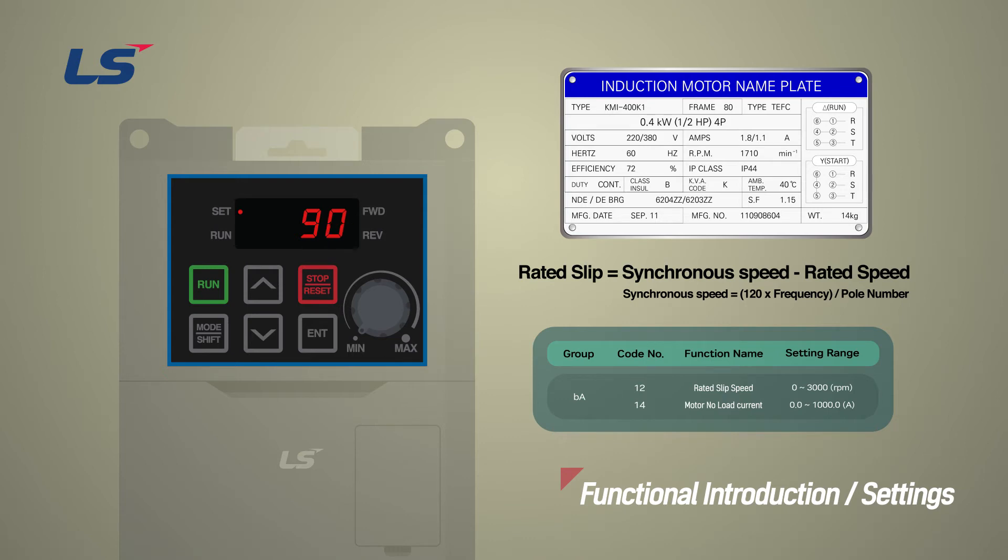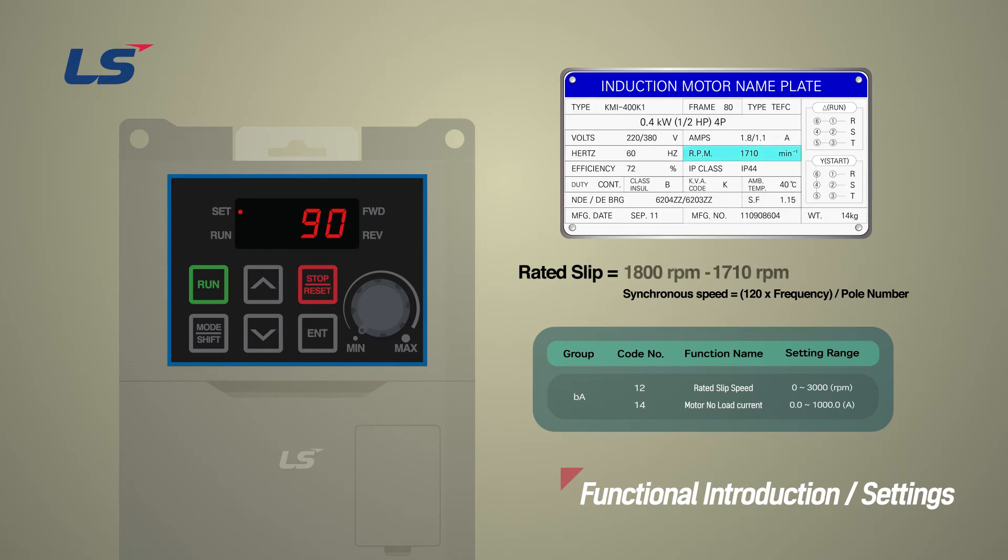The rated slip in G100 can be obtained by the formula of the synchronous speed minus the rated speed, and the slip of this motor is 1800 RPM minus 1710 RPM, that is 90 RPM.